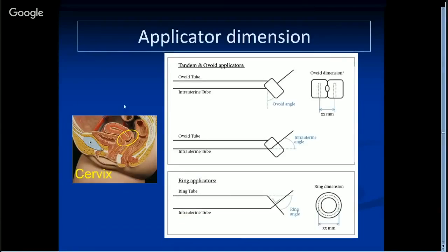Here is the picture showing you the applicator dimensions. I want you to know how we define the tandem angle — you see the angle here, that's the tandem angle. And how you define the ring angle, the ring tube — from here down here, that's the ring angle. The tandem and the ring should be perpendicular here, that's 90 degrees. That means if you use a 45 degree ring, you need a 45 degree tandem. Otherwise, you're going to have trouble.